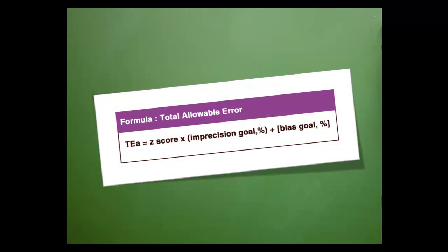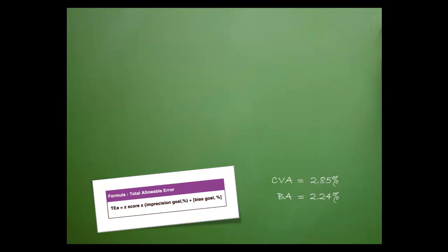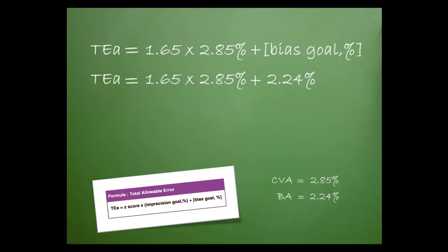Now that we understand all the components, let's practice calculating a TEA for serum glucose. Let's move our formula down into the corner, just in case we need it. These are our values for our imprecision goal percent CVA and our bias goal percent BA. We've chosen a z-score of 1.65 because we want to include 95% of the values within our target limits. Let's begin by copying down our formula and then substituting in the values. We multiply the z-score by the CVA and then add the BA. The TEA turns out to be 6.94%.